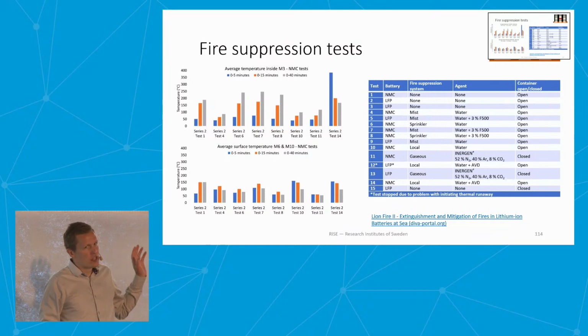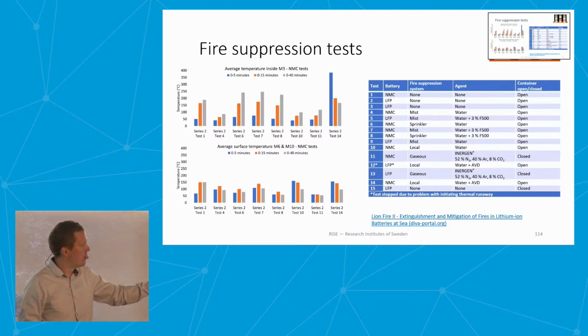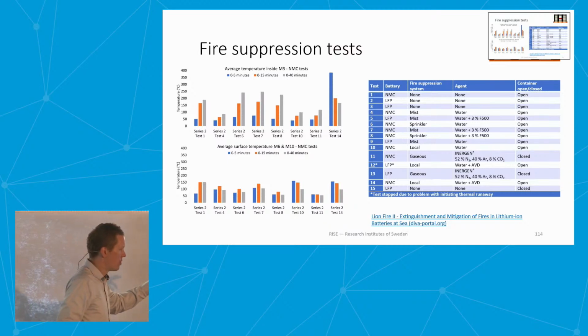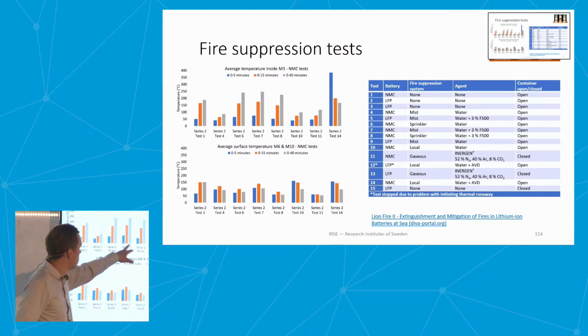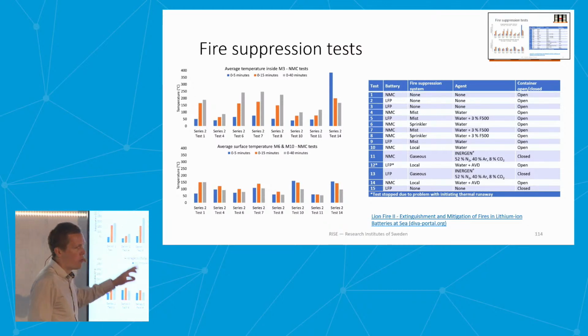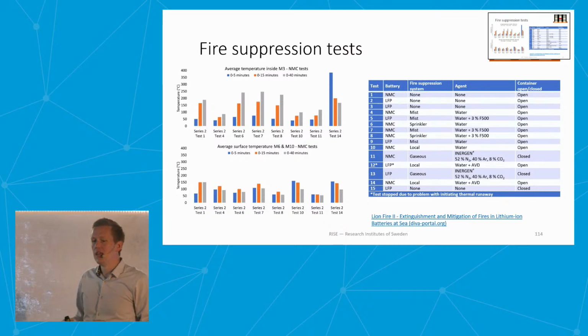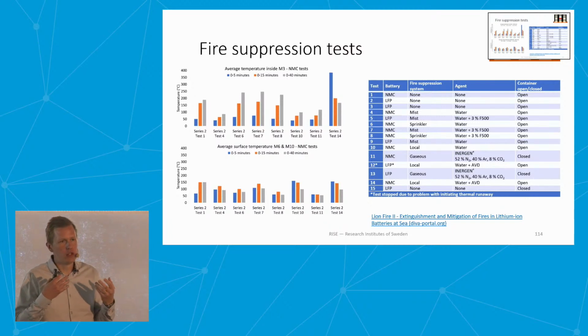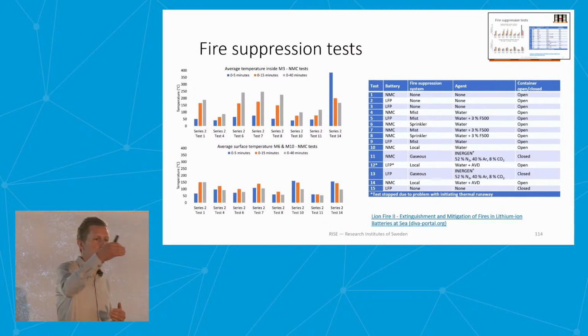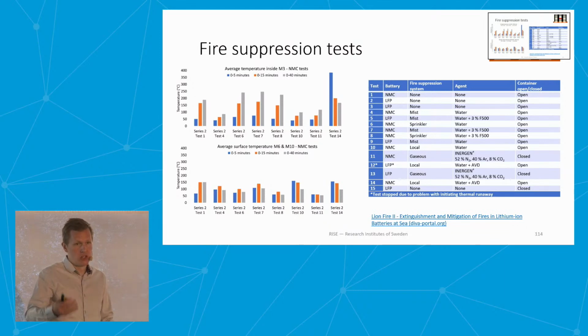But if I should say something about this, you could say that the gaseous system, as well as the mist system, at least for this module—these three here—performed well. The reason is that they were good at extinguishing flames also at the back of the rack, so they had good volume protection or access to the flames. That was the main fire spread between modules here—it was the flames.